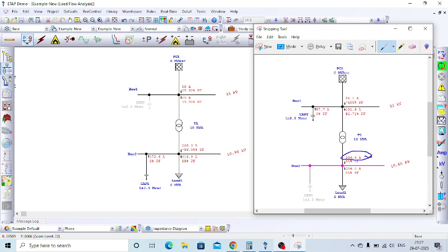But when we connected the capacitor bank in the low voltage side, the load remained at 85 percentage, but the transformer circuit is 266.9 ampere only. So there is a significant reduction of almost 40 ampere in the transformer feeder. Okay, transformer feeder.